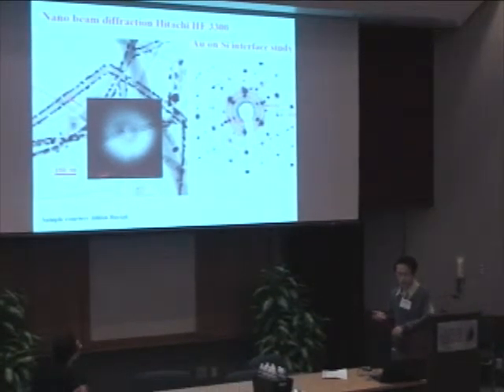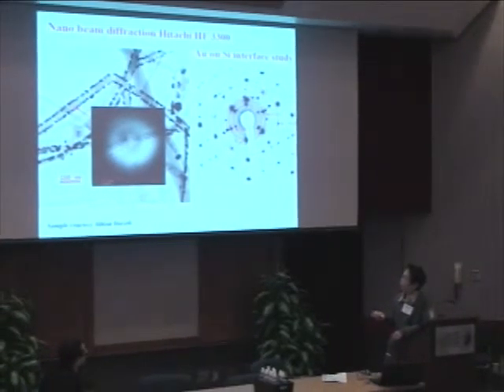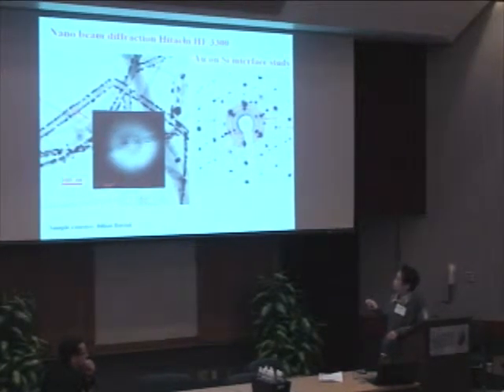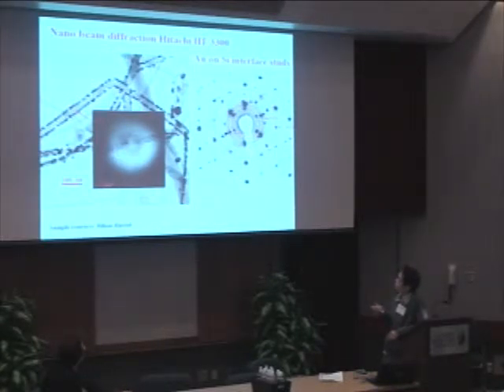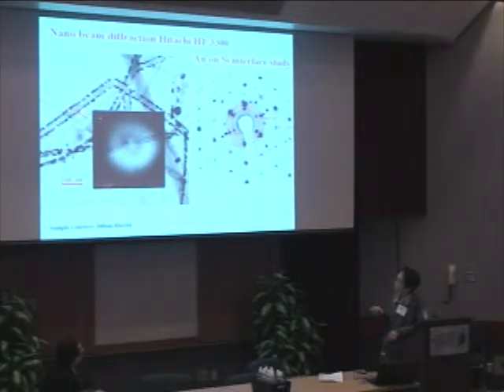In general, the electron diffraction technique gives you additional information that you cannot get from imaging, such as crystal structure and phases. On our machines, there is one unique feature called nanobeam diffraction — you can focus the beam down to less than 10 nanometers and get a diffraction pattern from just that small area, which provides a very unique technique to analyze interfaces and nanoparticles.